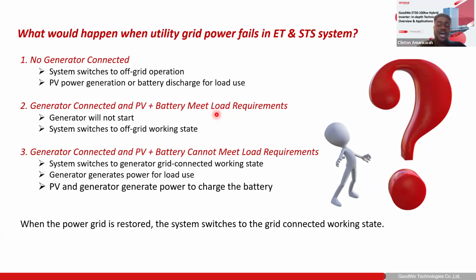Now, the third thing is, okay, fine, no problem. I have a diesel generator connected, I have my PV, I have my battery. There's a grid outage, but my PV and battery cannot meet the load requirements. So what is going to happen? If the PV and the battery can't supply the required load power, then the system starts the diesel generator. Using the signal cable, the system starts the diesel generator, and the diesel generator now supplies the full load to the house.